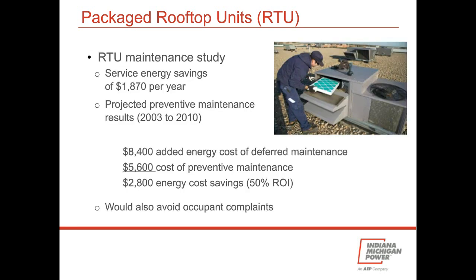Anyway, they had 5 service companies starting in 2010 return the unit to good working order. The first 4 performed just routine maintenance: rinse the condenser coils, check refrigerant charge.